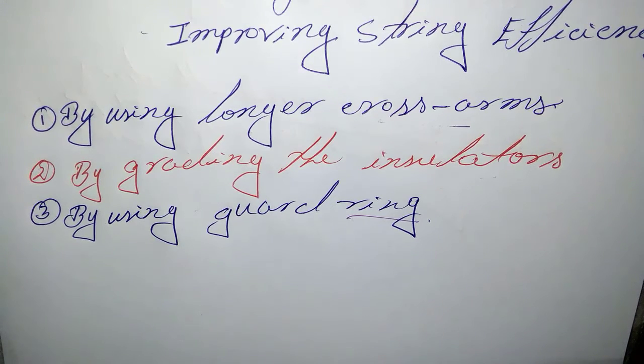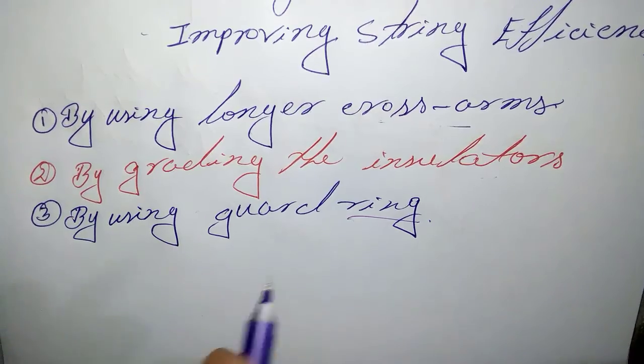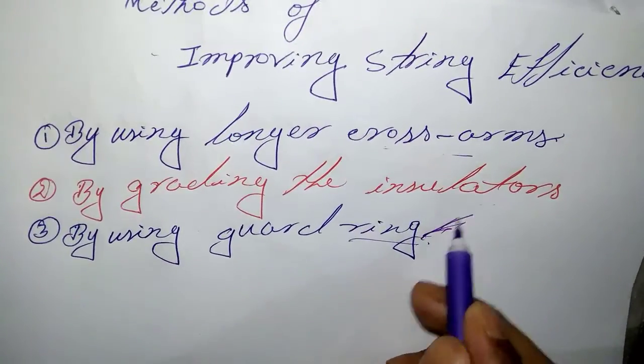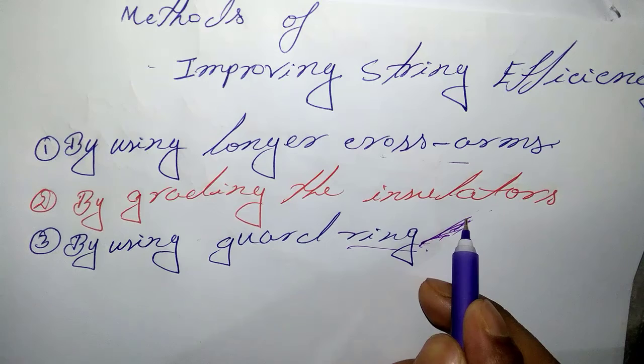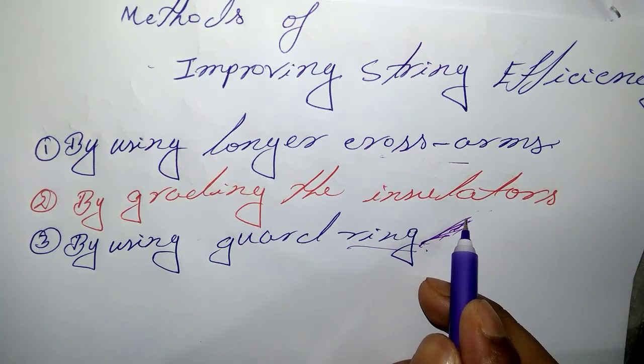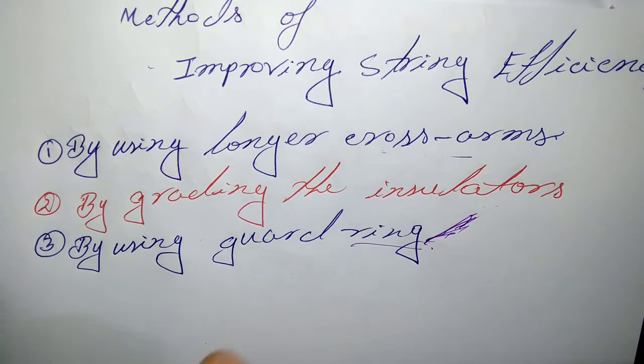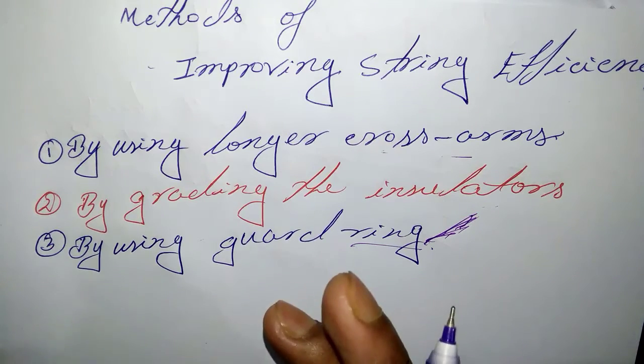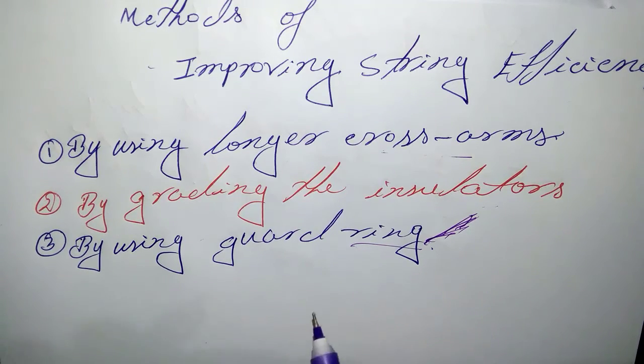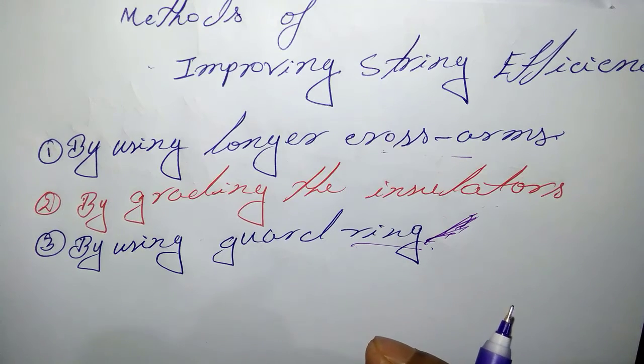The potential across units in a string can be equalized by using a guard ring, which is a metal ring electrically connected to the conductor and surrounding the bottom insulator, thereby improving string efficiency. Thank you everyone, see you in the next tutorial.